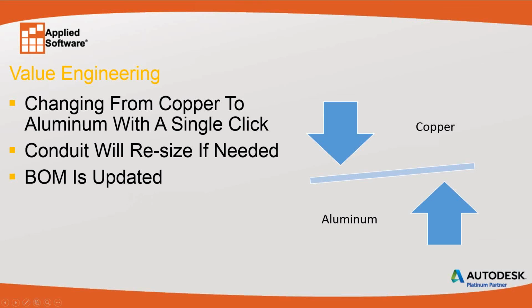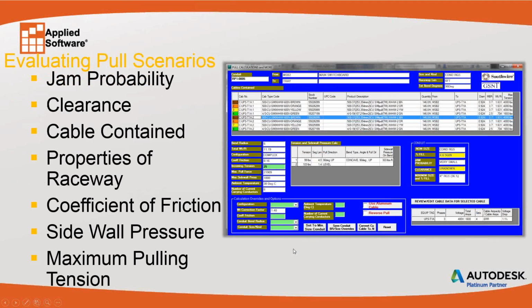Another great feature is Southwire's pull calculator. This allows us to evaluate pull tension calculations on our conduits, looking at sidewall pressure, jam probability, and clearance. It gives you a list of the cables contained, the properties of the raceway, coefficient of friction, and maximum pulling tension. It will also highlight and alert you to any area of concern outside the code or guidelines.